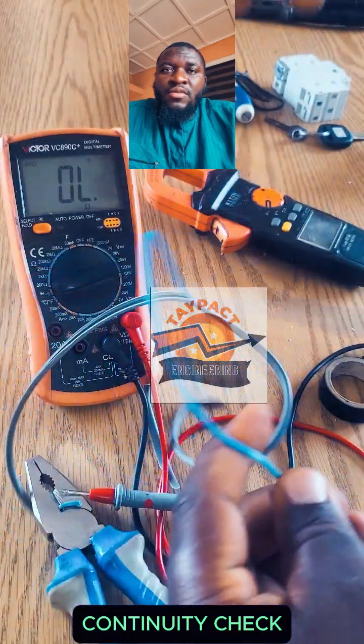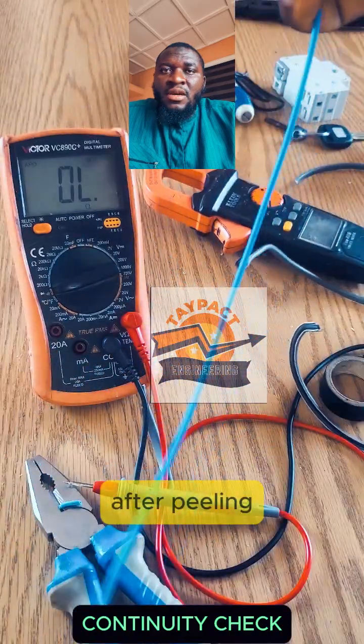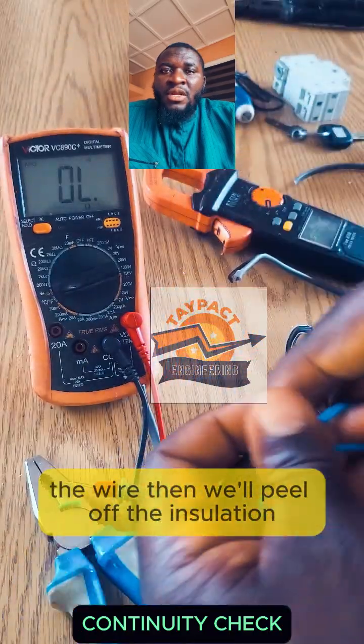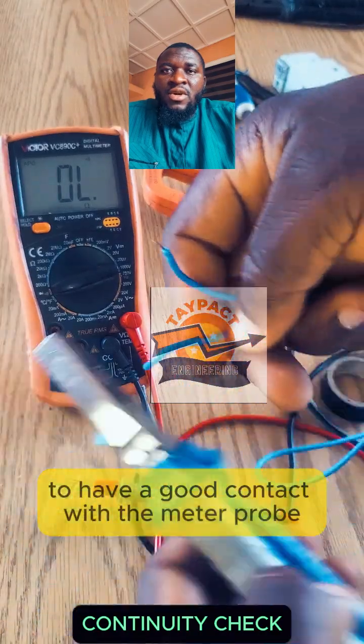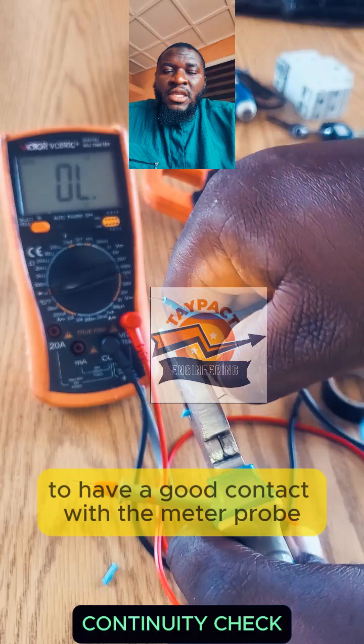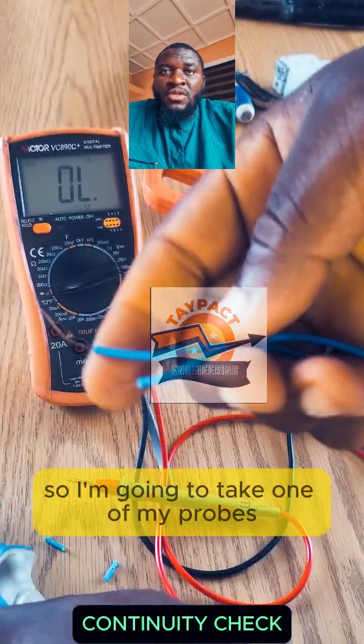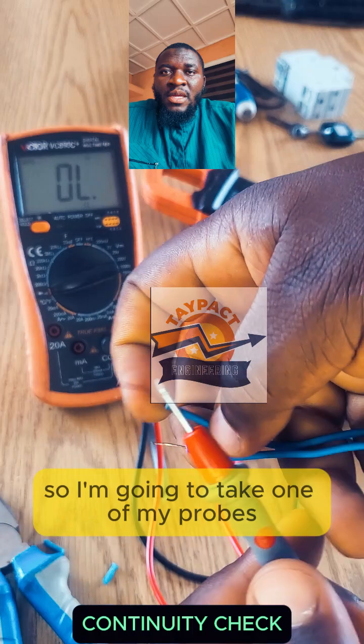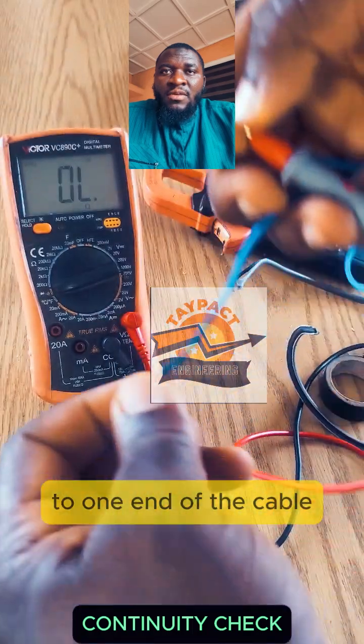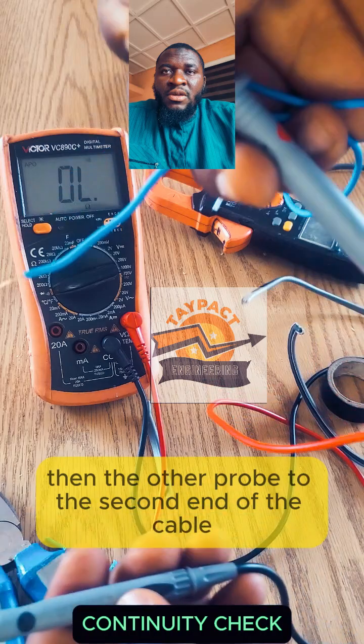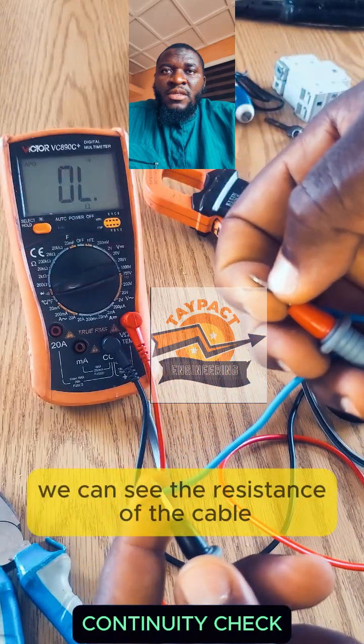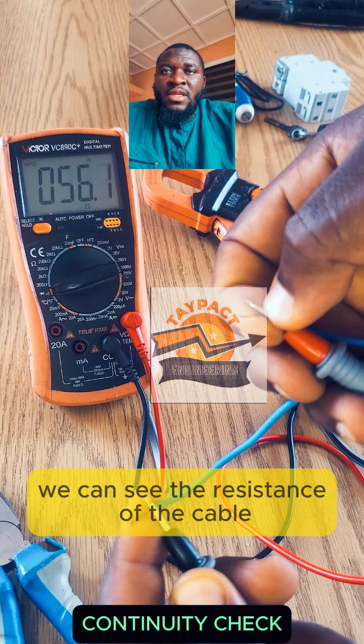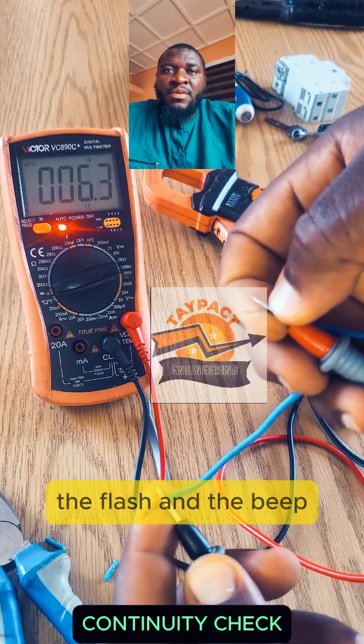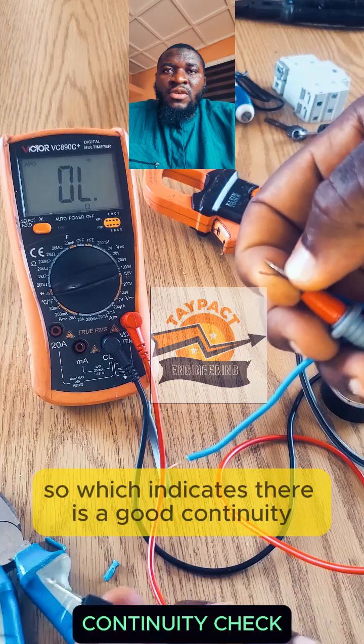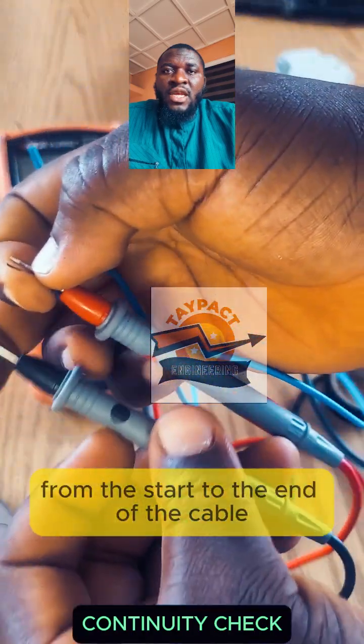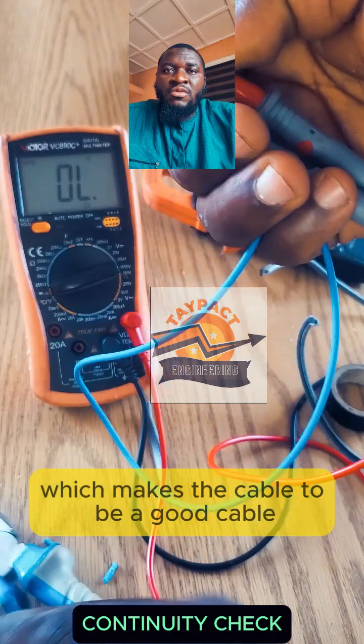So after peeling the cable, then we'll peel off the insulation, so we have a good contact with the meter probe. So I'm going to take one of my probes to one end of the cable, then the other probe to the second end of the cable. We can see the resistance of the cable, the flash and the beep, which indicates there is good continuity from the start to the end of the cable, which makes the cable a good cable.